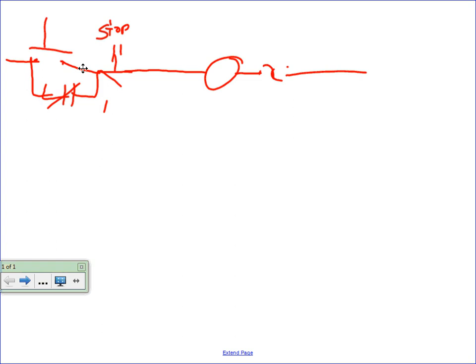So there's a control portion, and as far as control power, there's three different types. One's called common control, where we actually get the control voltage off the line voltage that the starter is running on. One's called separate control, where we may take control power for that starter from a panel board somewhere else and bring it in. The only thing you have to worry about there is that when the disconnect is turned off, everything in that enclosure has to turn off.